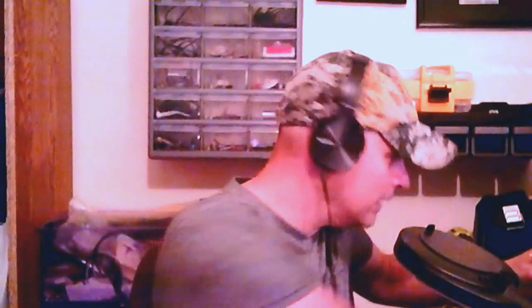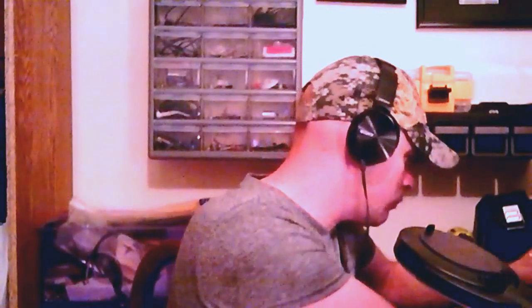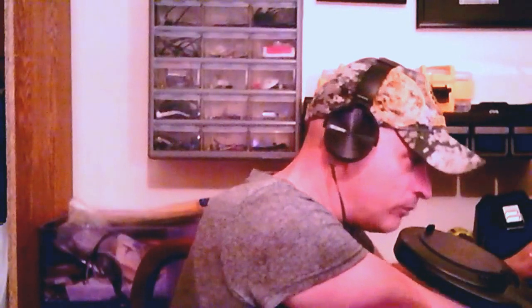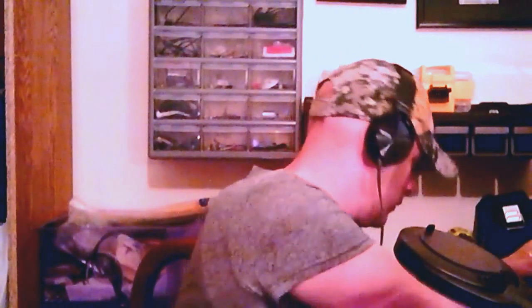There was a question on this. So let me give you a couple of sample motor sizes, and I'm not saying that I have any idea that this is even close to what might be on there, but I think the steps are pretty cut and dry, and they're not hard to wrap your mind around. Here's the deal: when we're doing a single motor by itself, just one motor with whatever that last overcurrent device is, we're going to round that down because of the way it's written in 430.52. So let's say I had a single motor sized as a 25 horsepower, 208 volt motor. The FLC value of that motor is where you're going to start.